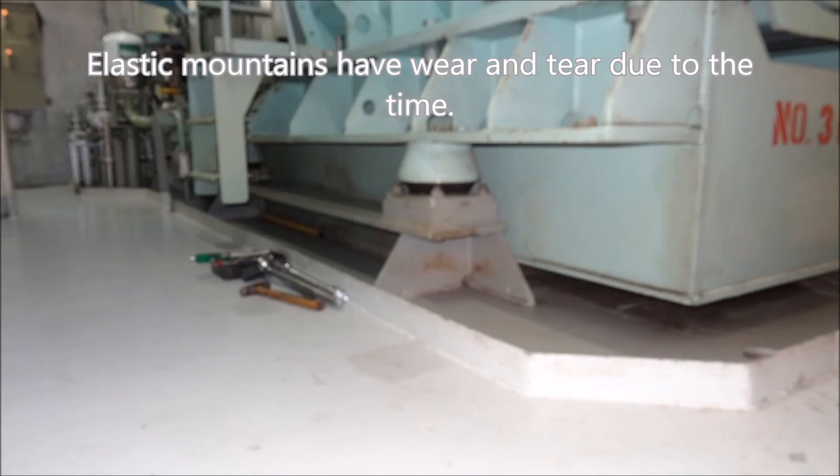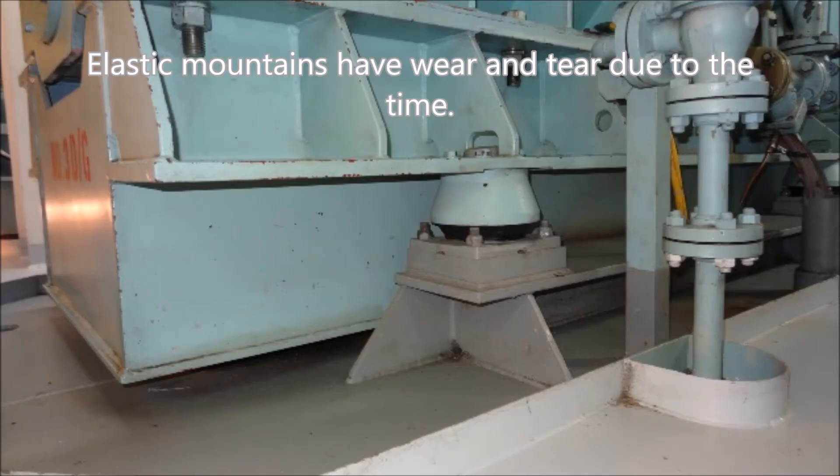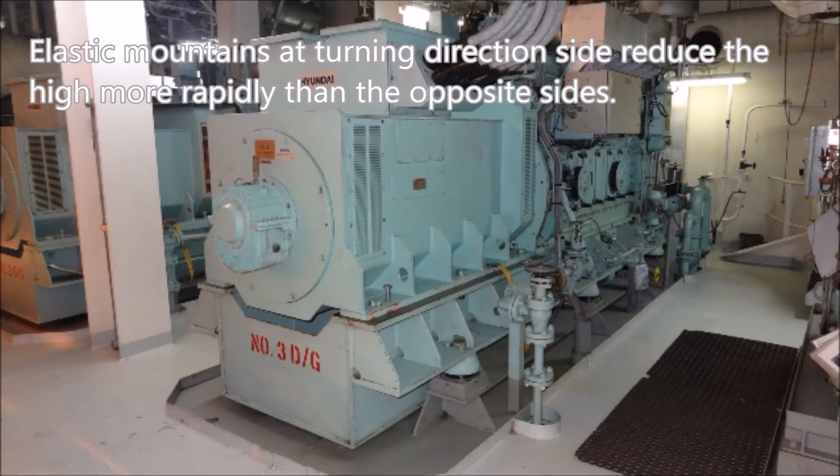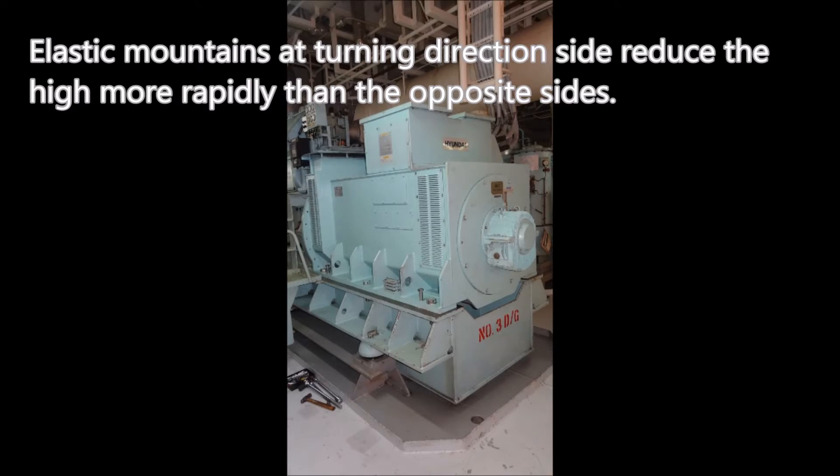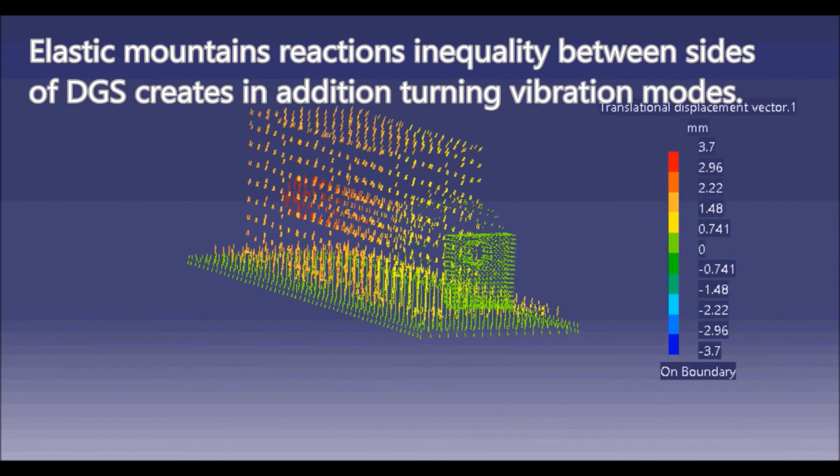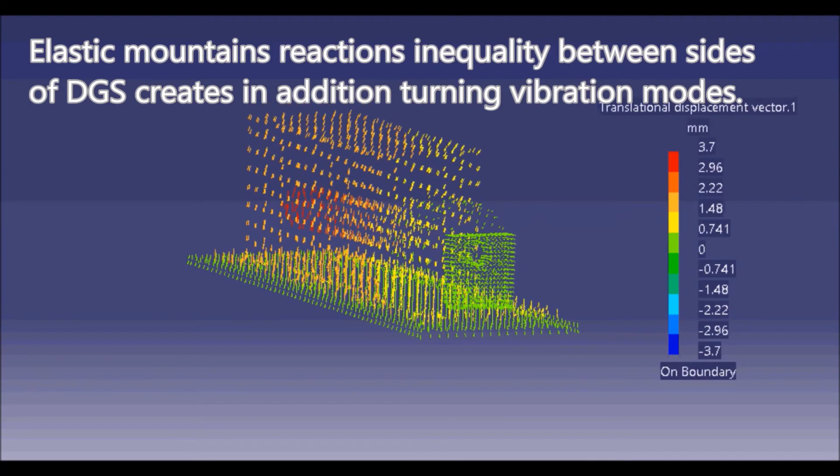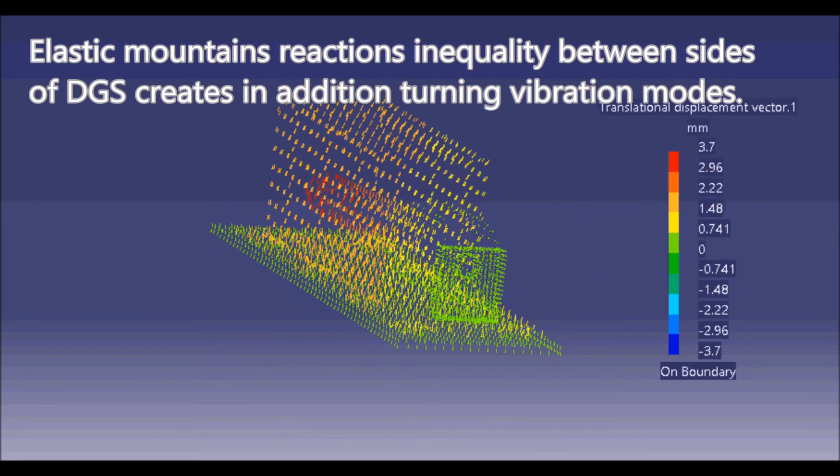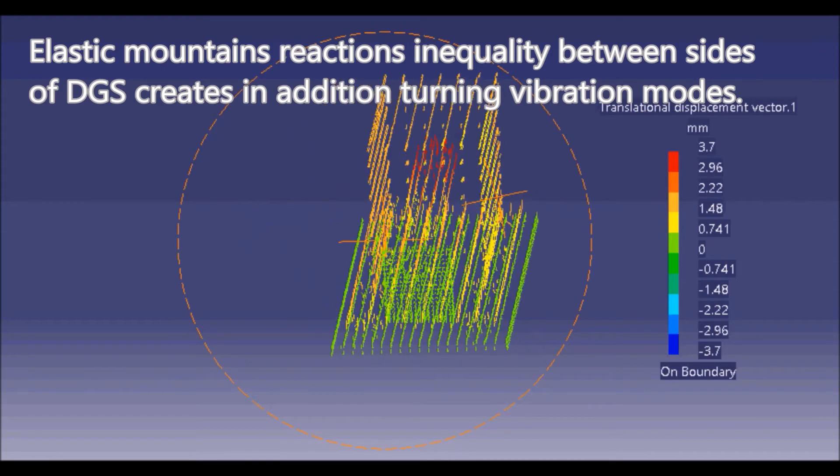Elastic mountings have wear and tear due to time. Elastic mountings at the turning direction side reduce in height more rapidly than the opposite sides. Elastic mounting reaction inequality between sides of DGS creates in addition turning vibration modes.